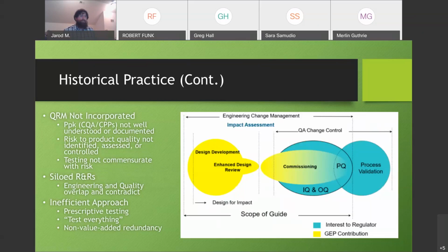So there was a lot of activities built around user requirements and those upfront document deliverables without really understanding the end process and how that impacts critical quality attributes of the product and critical processing parameters of equipment in the process. In alignment with that, the risk to product quality was not appropriately identified, assessed, or controlled within the historical models. And the testing was also not commensurate with the risk.